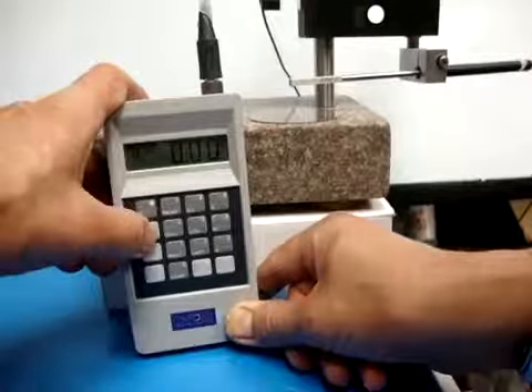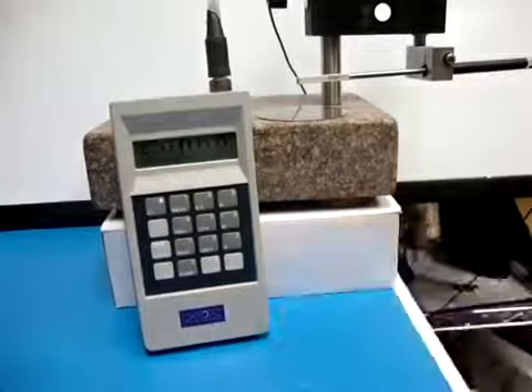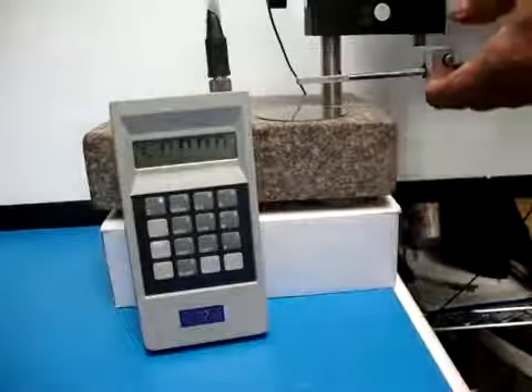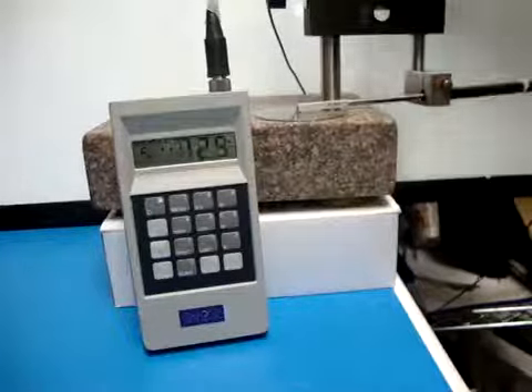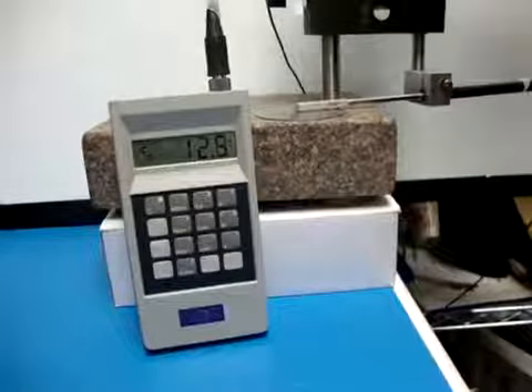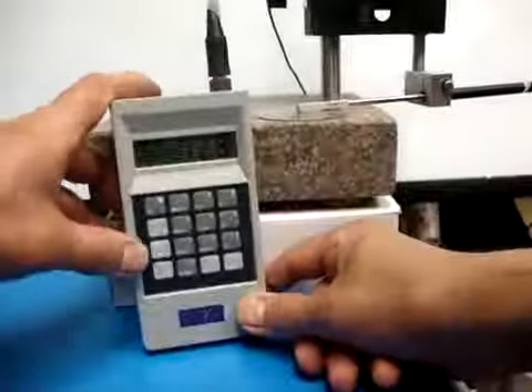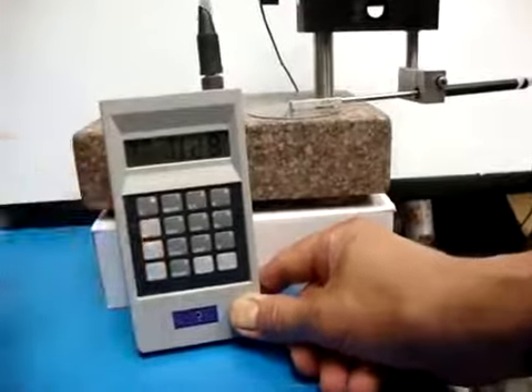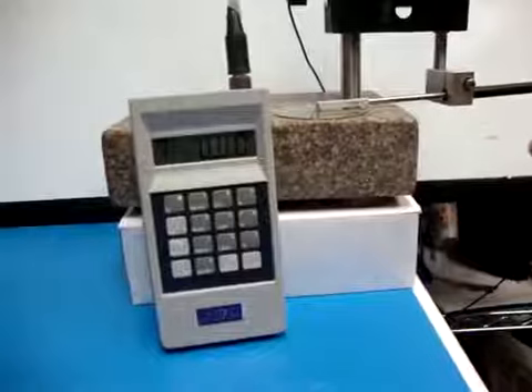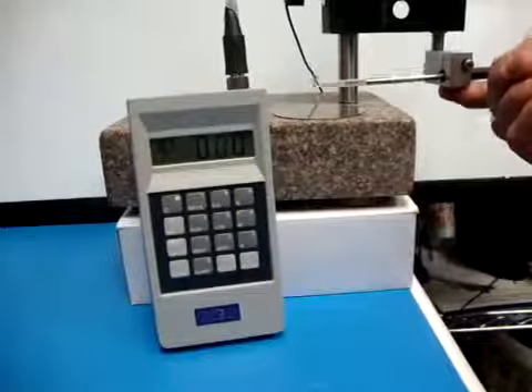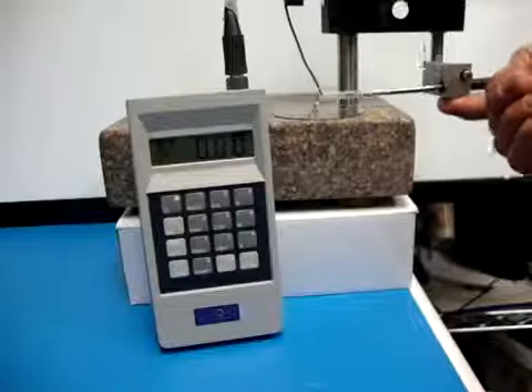So I'm going to hit the button called cal, and so now it's waiting for me to place the probe down on the base. Placed on the base, I'm going to hit 0 units, and that way it'll be zeroed out to the base, and that way each subsequent measurement comes out 0.